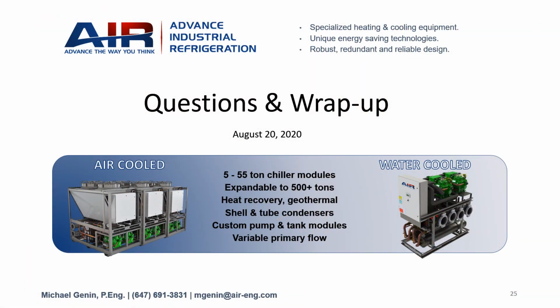So now we'll take some questions and wrap up the presentation. A couple questions. Can the chiller be reversed to act as a heat pump? The short answer is yes. A lot of instances it's common for the air-cooled chiller. This goes beyond the scope of heat recovery, but the air-cooled chiller can act in chiller mode, heat recovery mode, and then have an air source mode. So if your cooling load disappears in wintertime, let's say, the chiller can still provide some level of heating by extracting heat out of the ambient air.